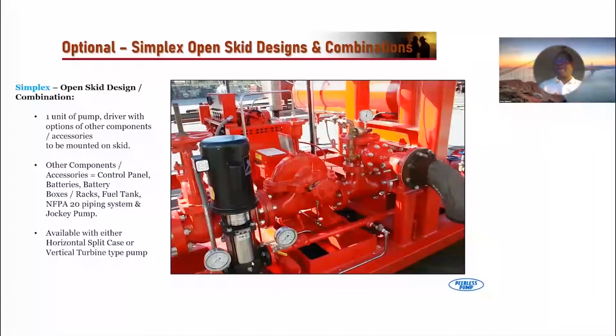We can do a little bit of a compact one where we'll give you an optional simplex open skid design. In the picture right here, it's a diesel pump with a jockey, with a relief valve, with an overflow cone, with the diesel tank, everything all compact. We've done all that work for you. It's almost semi plug and play, meaning that you bring your suction piping into it and your discharge piping out. You plug your power into the controller to charge your batteries. Everything is all done and ready to go. And you probably need to put some protection at the job site because NFPA requires that the minimum room temperature of the pump has to be 40 degrees Fahrenheit. 40 degrees Fahrenheit is roughly 4 or 5 degrees centigrade, if you need to interpret that.